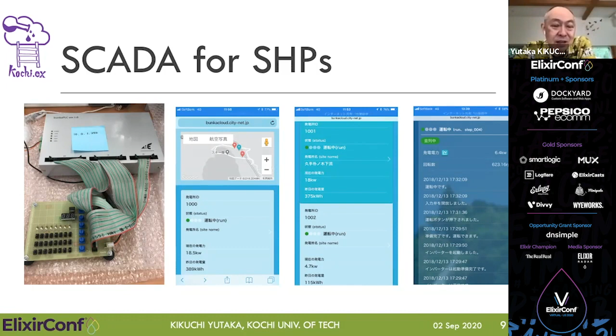I want to briefly explain the SCADA system of small hydropower plants. This diagram shows a typical small hydropower system with power inverters. Water from the river comes to a head tank to remove leaves, silt, and sand. Water gets high pressure through a penstock connecting the head tank and the inlet butterfly valve. Once the inlet valve opens, the turbine rotates and drives the generator. The inverters regulate generated electric power, and the transformer adjusts the voltage for connection to the power grid. SCADA must gather all states of the plant and regulate each piece of equipment, report the condition to the plant operator, and process orders from the operator via the internet.